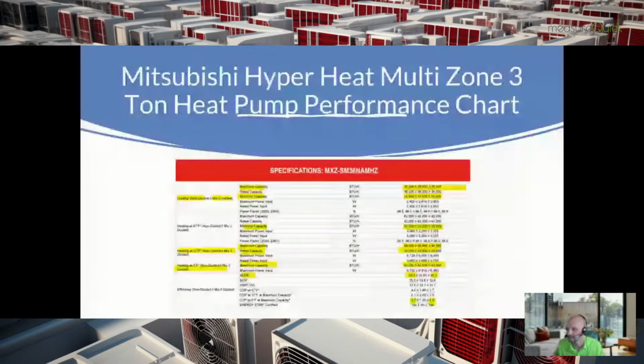Okay, so look at my highlight at the bottom there. I'm sorry, guys. You can see the difference in SEER. Now look at the difference in coefficient of performance, but look at the big no in the middle where it says Energy Star certified. If you're mixing ducted and non-ducted, Energy Star is saying we're not putting our stamp on that quite yet. They haven't proven that they can maintain these efficiencies at all times at the rated condition. So that's just all stuff to be aware of, guys. There's a lot of nuance when you're dealing with these heat pumps.